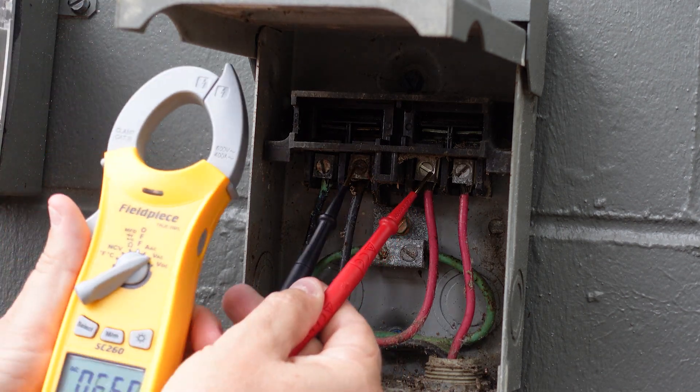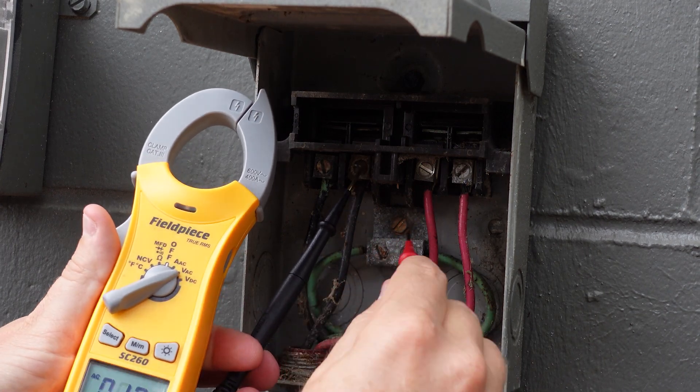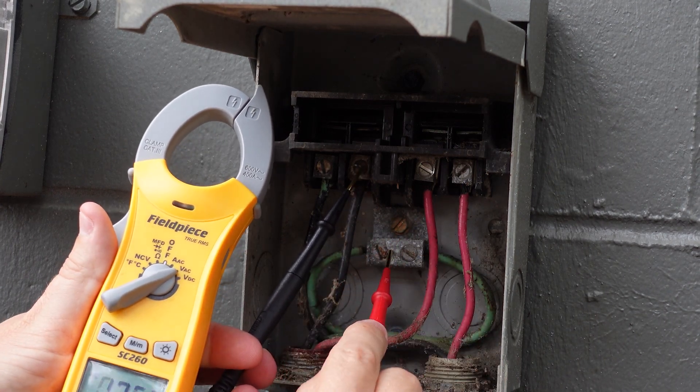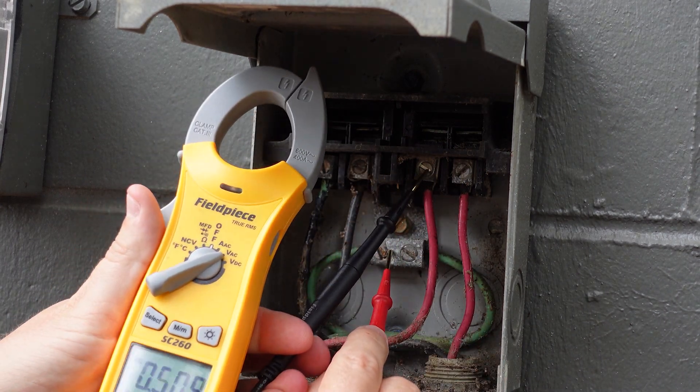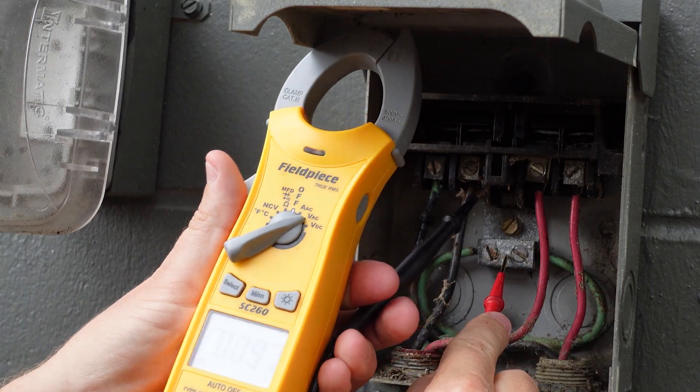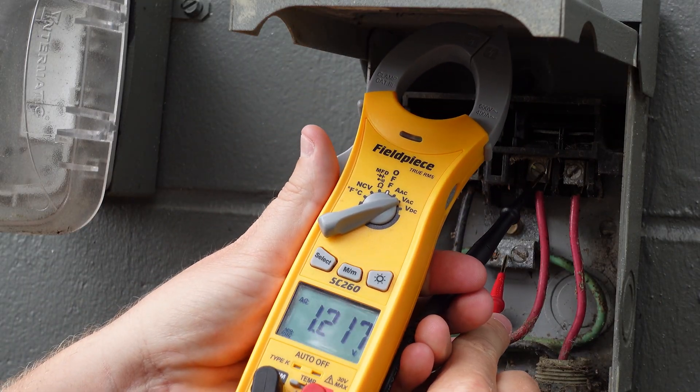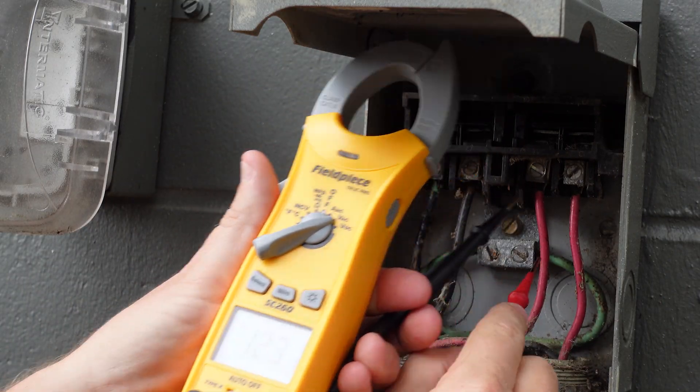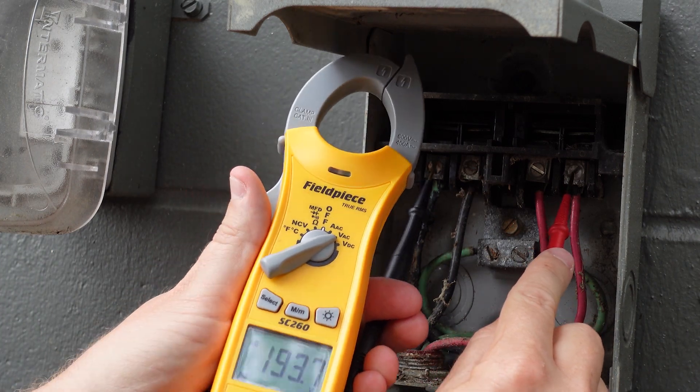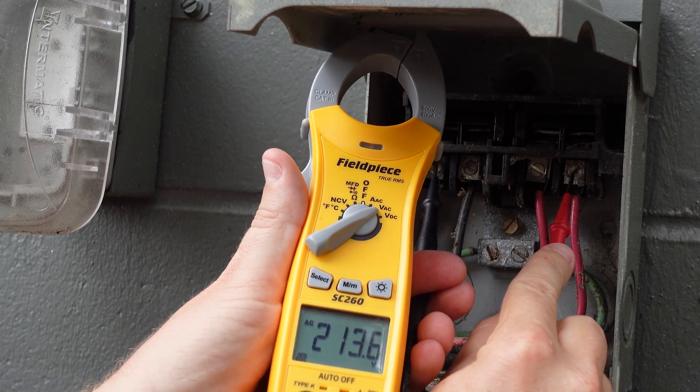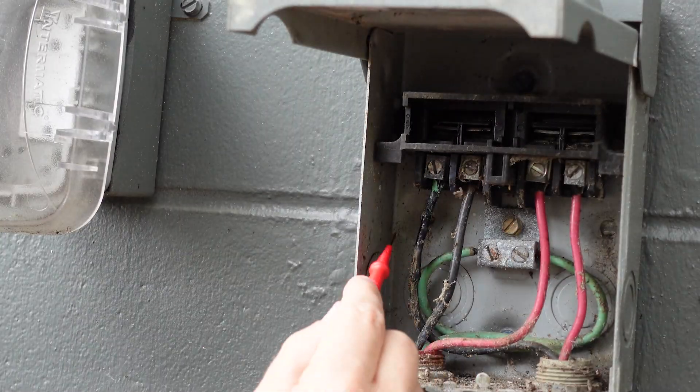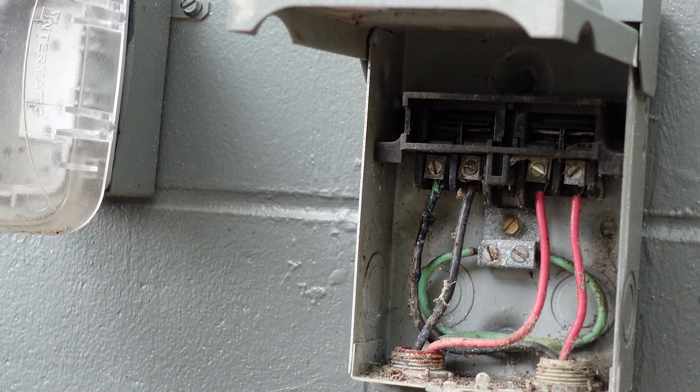But also as a safety check, we're going to check from each side feeding our unit to ground as well. So I'm measuring from each leg to ground as a safety check. And then coming in, we can see we have power applied. And this definitely needs to be addressed.